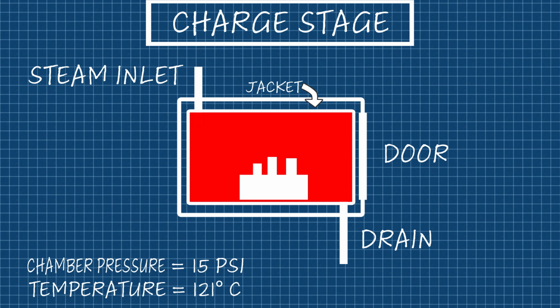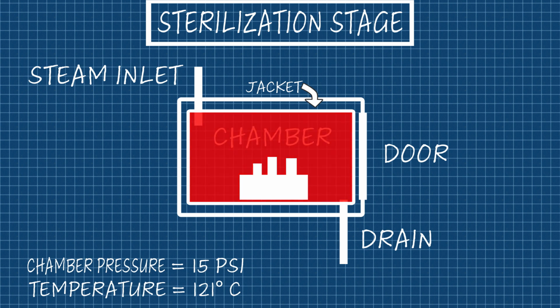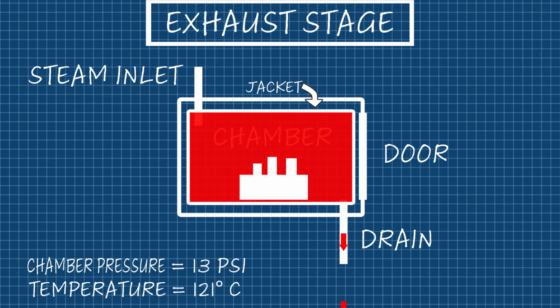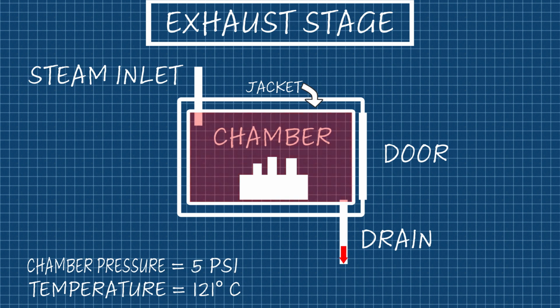Once the autoclave reaches temperature and pressure, it will begin the sterilization stage. The autoclave will remain in this stage for a predetermined amount of time to sterilize the load. Once the sterilization stage is complete, the exhaust stage will begin. The steam will exit the chamber through the drain. The exhaust stage can be either fast or slow depending on your cycle choice. Gravity cycles will use a fast exhaust method, and liquid cycles will use a slow exhaust method. The slow exhaust is to prevent boil-over. Once all of the steam has been exhausted, the chamber pressure gauge will read 0 psi. It is now safe to open the autoclave door.